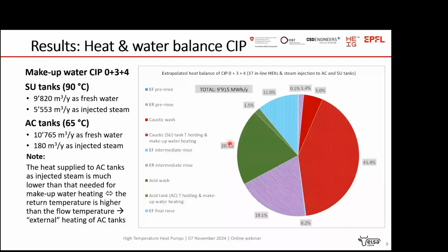One thing which is surprising is that the acid tank, in fact, requires very little heat for temperature holding, because the return lines have a higher temperature than the flow temperature. So it is heated externally by the circuits, or the equipment, which are cleaned. Yeah, because in the soda caustic tank the temperature holding is very large, while for the acid tank it is quite low, or very, very small.